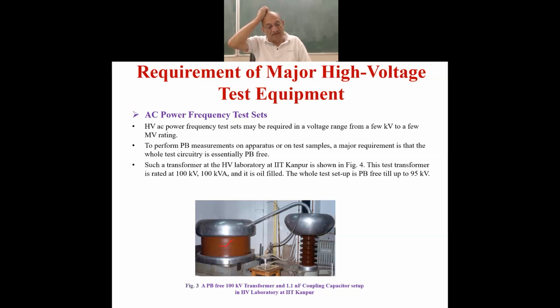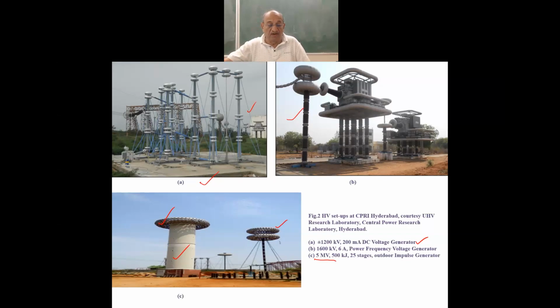Obviously, when we go for still very high voltages, as we discussed, 1200 kV DC and 1600 kV AC, it's very difficult to make the equipment absolutely PD free. There may be some magnitude of partial discharge going on in the equipment. To take care of this, you can see the toroid rings here. These are called toroid rings. This is also a toroid ring, and here these are the toroid rings. Connectivity is made with such large dimensional tubes.